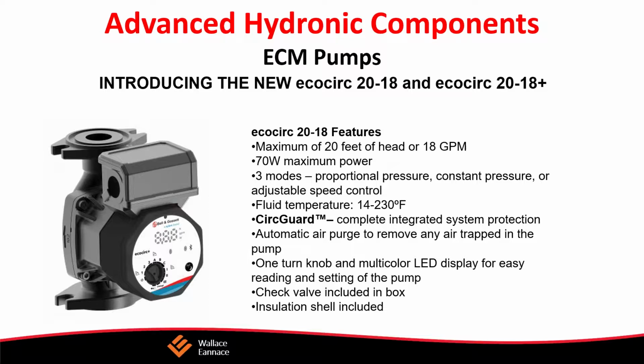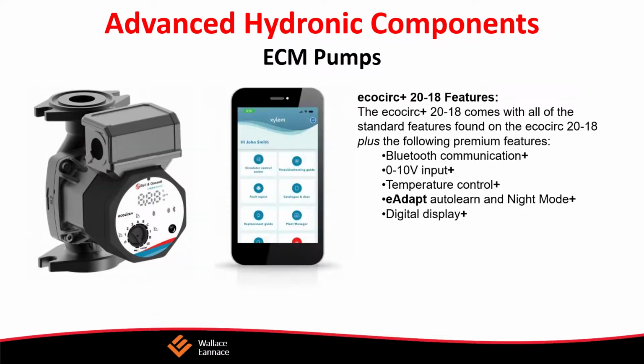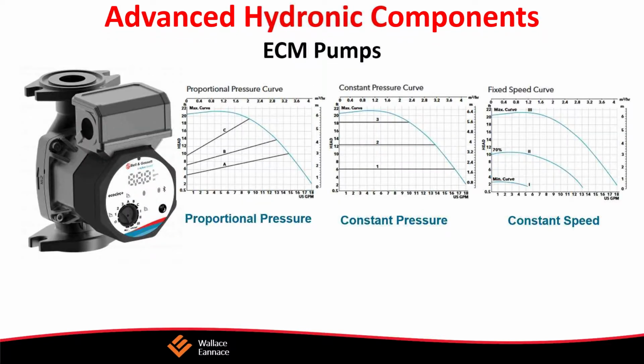And as you can see, if we have a 10 watt pump, 40 of them is going to give us 1,000 BTUs per hour per watt. So our efficiency has dramatically increased. From those simple numbers, we can see that ECM pumps work. But what is available and when can we use them? Let's take a look at what is offered for ECM pumps.